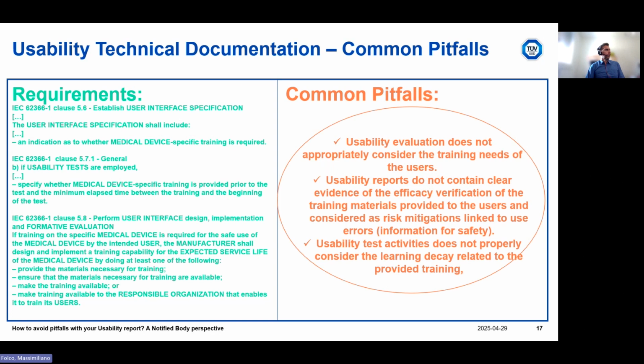Okay, let's move to training material and to training needs. Here we have a group of requirements from the standard that basically requires the following. The user interface specification for a medical device has to specify if a medical device specific training is required, based on the characteristics of the device and on the intended users.